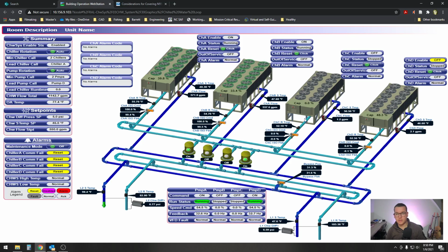Earlier, when chiller C had an issue and it had to fire up B, the time it takes for B to fire up, it actually got up to 51, and then got as high as like 53 degrees supply temp. And once we cleared the alarms on C and it was healthy again, the system said, good, I'm so far away from set point, I need some help. It turned on a third chiller, and all 3 were running to get this number back down closer to 46. And once that number got close to 46, it kicked this unit off automatically.